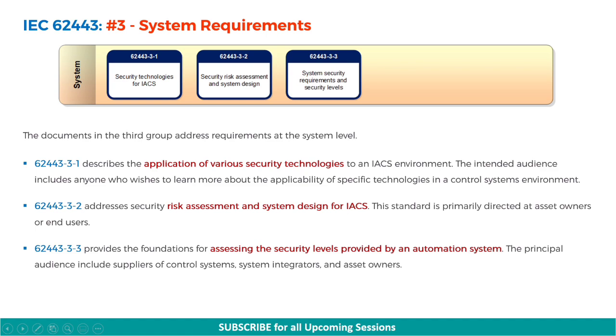The third section is Systems Requirements, that is 62443.3. The documents in this group address requirements at the system level. 62443.3.1 describes the application of various security technologies to an IACS environment. 62443.3.2 addresses security risk assessment and system design for IACS, primarily directed at asset owners or end users. 62443.3.3 provides the foundations for assessing the security levels provided by an automation system, with the principal audience including suppliers of control systems, system integrators, and asset owners.